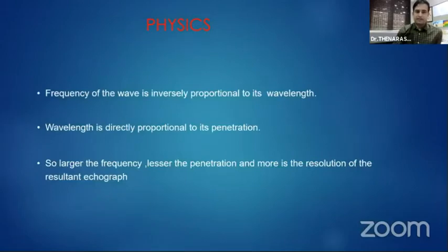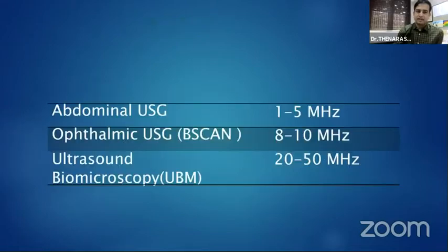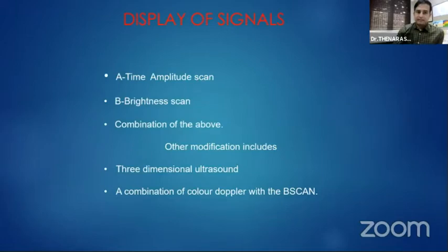The frequency of wave is inversely proportional to its wavelength, whereas wavelength is directly proportional to its penetration. Hence, larger is the frequency, lesser is the penetration, and more is the resolution of resultant echographs. These are the different frequencies used in different ultrasound probes. We have time-amplitude A-scan, brightness B-scan, combination of the above, and in addition, three-dimensional ultrasound and combination of color Doppler with B-scan.